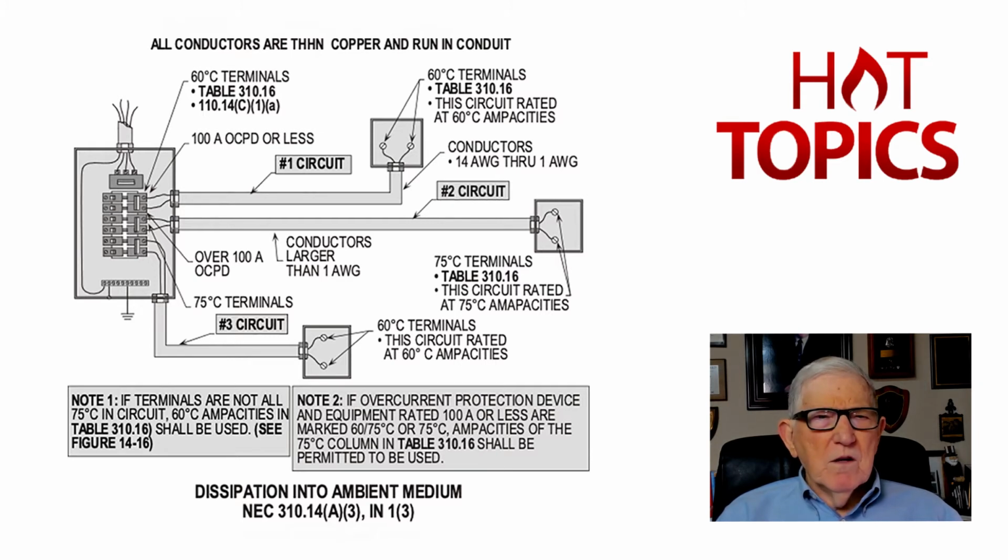Now you say, well, wait a minute. I'm looking at Note 2 here below, and if you look at the third line down, 60/75 degrees C, and the equipment 75 degrees C, your breaker's 60/75. Then you could cable it in conduit here at 75 degrees C. Now when you go to your Table 310.16, you just need a number 3, good for 100 amps. You see that?